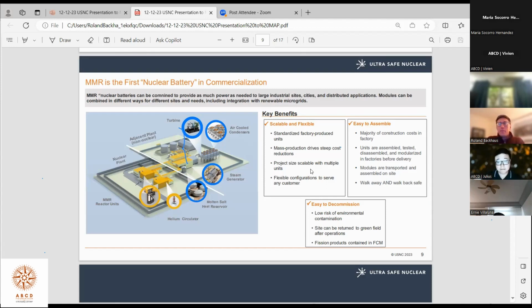If a partner needs 60 megawatts electric, for example, and does not want redundancy, that's four MMRs with the balance of plant — four micromodular reactors with the balance of plant. If the need increases after initial siting and operation, we can come in and add nuclear batteries in series right on top. If demand goes down, all we need to do is decrease the helium flow rate through the core, and that lengthens the amount of time the battery will last.